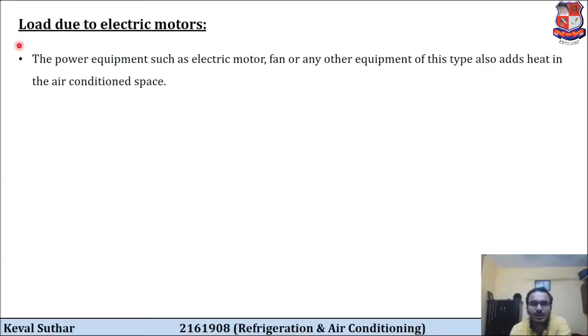Now the next is load due to the electrical motors. The power equipment such as electric motor, fan or any other equipment of this type also adds heat in the air conditioned space. The heat gain from the electrical motor is given by this formula, that is Q electrical motor is equal to power rating of motor in kilowatt divided by motor efficiency multiplied by load factor. Here the load factor is the fraction of total load at which the motor is working. That will be the heat gain from the electrical motor.